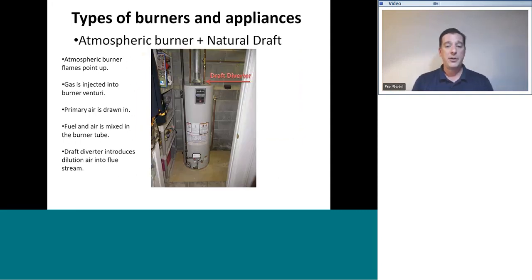So what about the draft diverter? Here's a draft diverter. Most water heaters have a draft diverter. You can tell by the gas valve on this water heater that it is pretty recent. This one was probably installed within the last handful of years or so, 5 years or less. This opening here is a draft diverter. It should be drawing air in at all times, especially when the burner is firing.